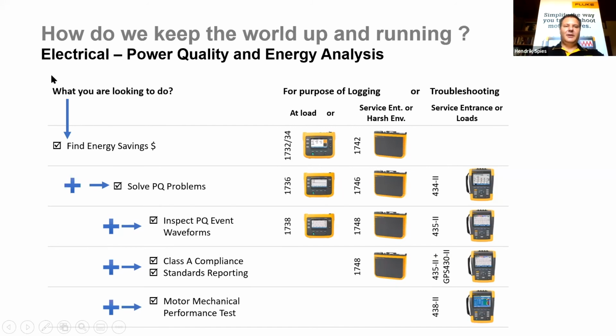Okay, so first, you must determine what you are looking for. If you want to do energy savings, then typically for logging, we've got the Fluke 1732, 1734 series of power analyzers, power quality analyzers. Or if you want to go to a harsh environment, or we want to do additional functionality, then we've got our Fluke 1742, which you'll see does not have a screen. So this is popular with consultants and electrical technicians that actually need to do some energy saving measurements and maybe look at the load itself.